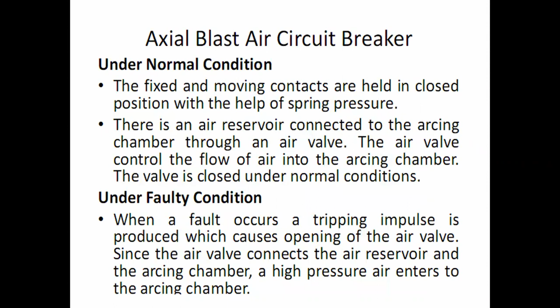You can see in this picture representation, and also by the names, axial blast, cross blast, radial blast. So we have only one circuit breaker, but how the blast of the air is thrown out and how it impacts the contacts of the circuit breaker, accordingly the circuit breaker can be classified. If the blast is in the same direction as the arc, then it is called axial blast type. If the blast of the air is perpendicular to the path of the arc, then it is called cross blast. And if the blast is directed radially, then it is called radial blast type. So you can see that we classify the air blast circuit breaker according to these three types: axial blast, radial blast, and so on.